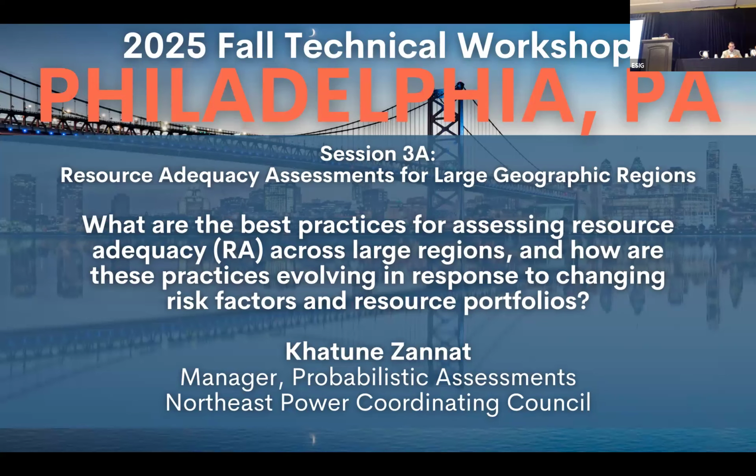in December. In addition to that, last year, we also standardized how we model wind and solar profiles as part of the wide area probabilistic assessment. What we did was to basically capture simultaneous wind lulls or weather-driven variability in NPCC's multi-area probabilistic reliability assessment. So these are the improvements we have been making.